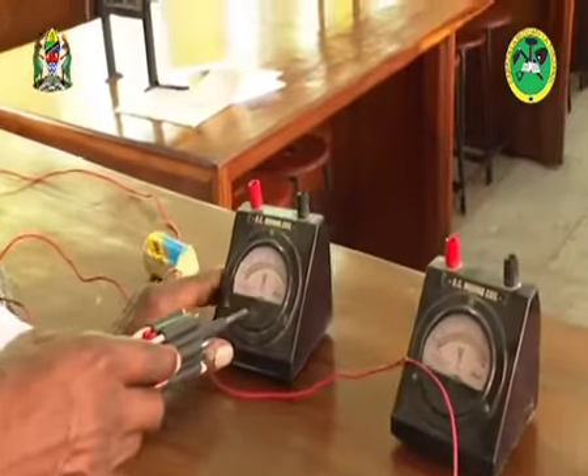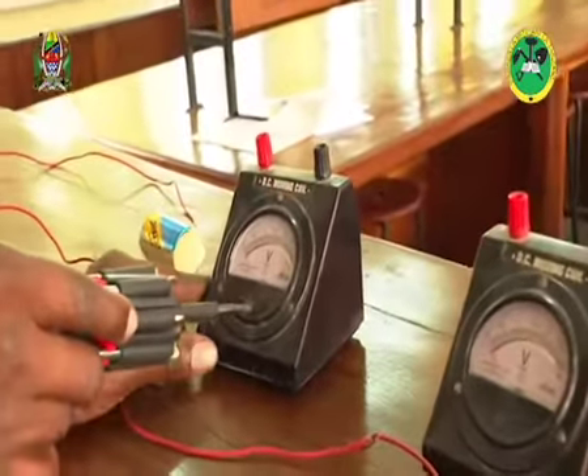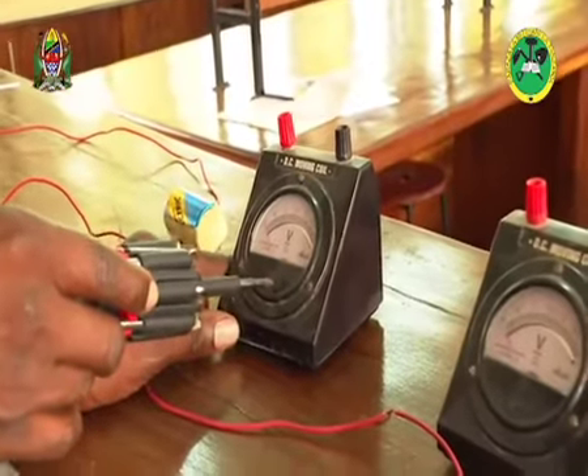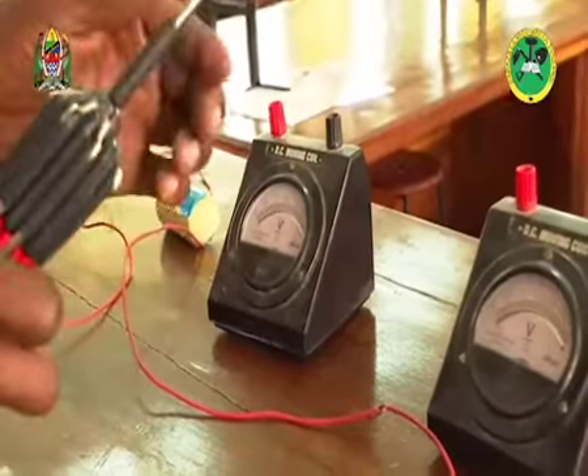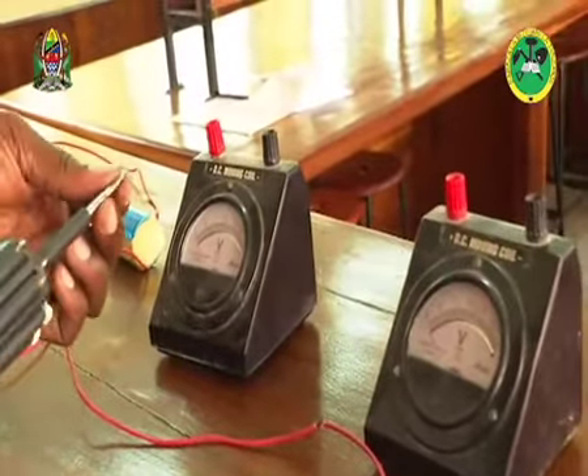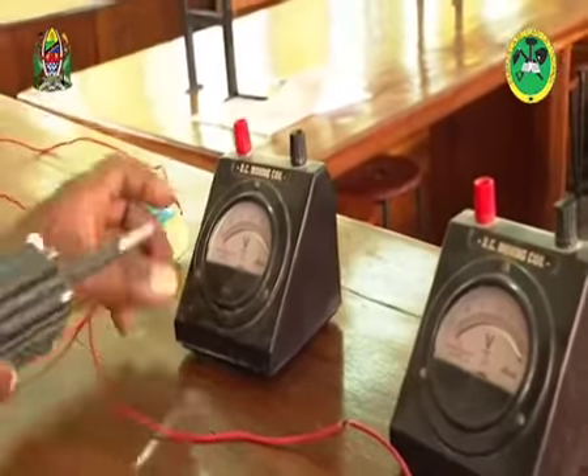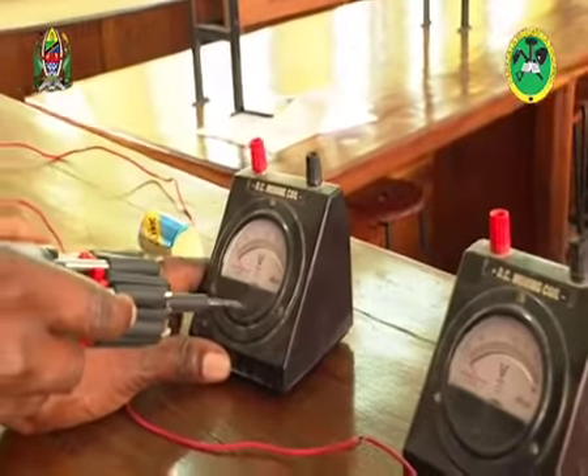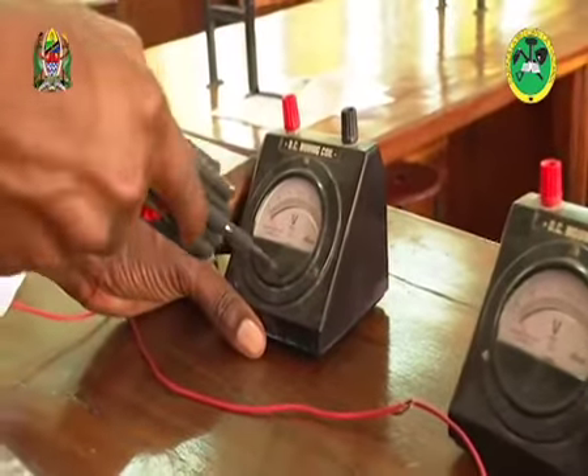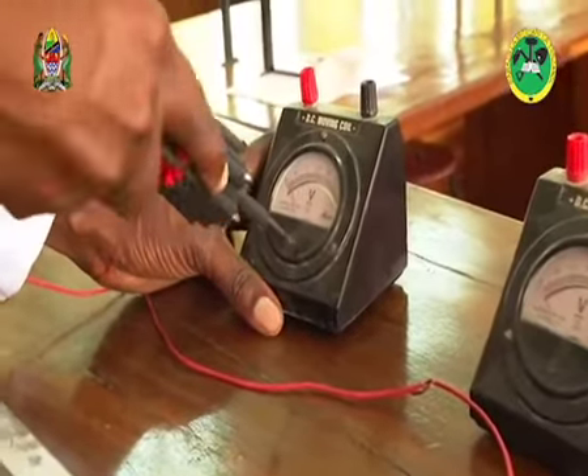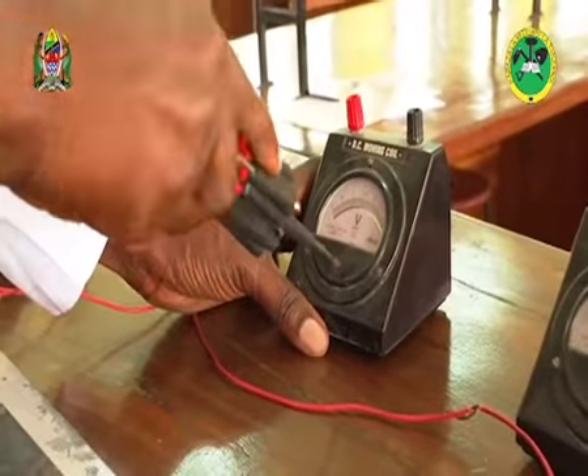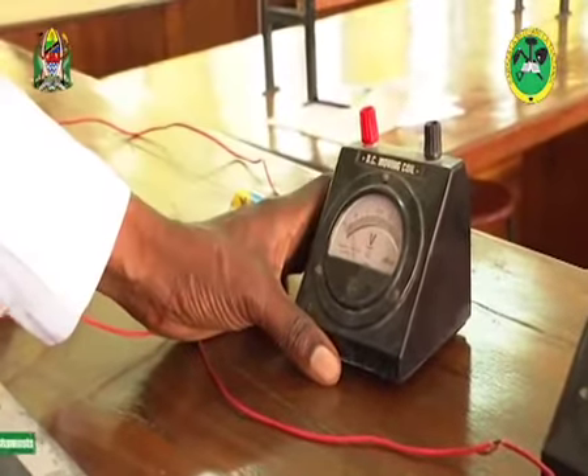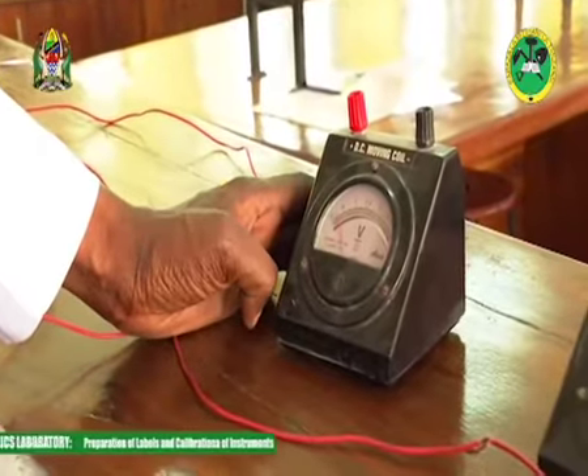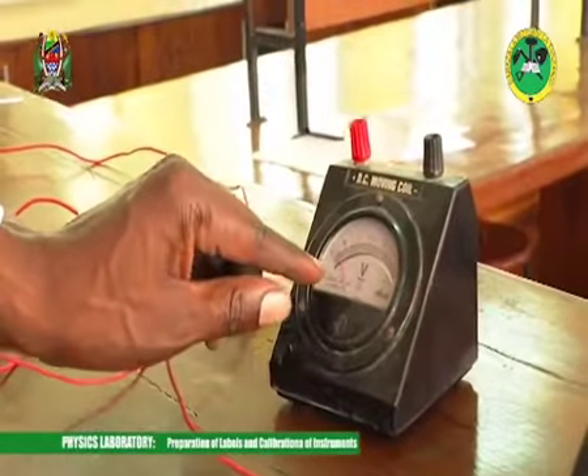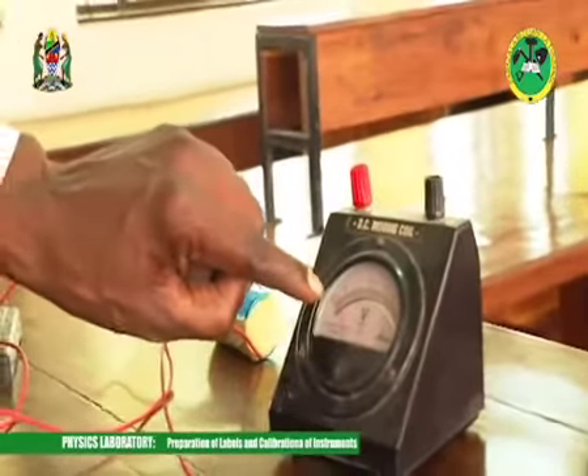Here is the knob I was trying to tell. This is the adjustment mode. It has an arrow in between where you can place a screwdriver. So this is what we do here at the center. Now you can adjust this left or right. Now you can see if I adjust left or right, it keeps moving. Now have a look. If I put it here, you can see this is an incorrect zero error adjustment. So there's no way you can take the reading when this arrow is not pointing to the zero mark.